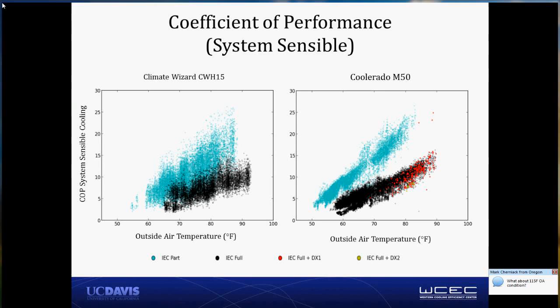So, Brad, I suspect you're getting to the question of whether or not the Climate Wizard is doing a better job of carrying the load and therefore doesn't need to run with vapor compression cooling. The answer is no, and it's not conclusive. Each of the zones served by these equipment are significantly different. That's one of the main points we're learning from all this field evaluation. You should be strategic about where you're applying some of these indirect evaporative retrofits.